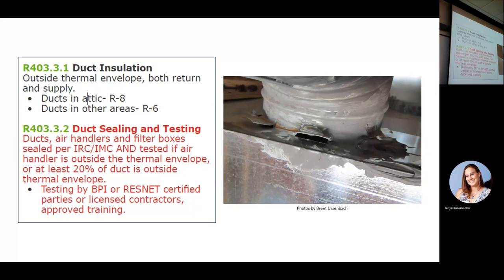So what we did is we cut them out, and then my guys had caulk guns with sealer, and we sealed them all as we put them in the duct. And so the only thing we had to seal were some of our cleat joints and stuff like that after the duct system went in. And some of those we even sealed as we were putting together. Before we bent our drives over, we put some sealer there and sealed them up.